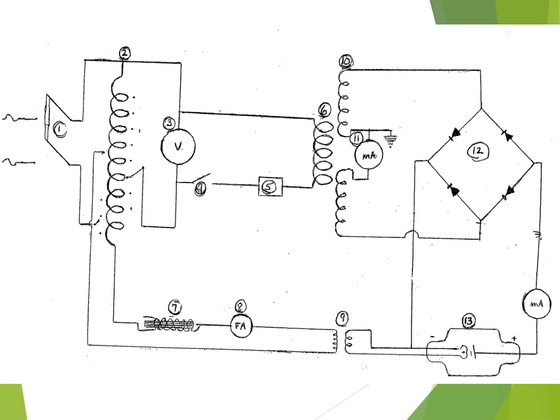Now here's a picture of our circuit. I'm going to start off with the first part. The very first portion is the primary circuit, and that's everything from number 1, which is the electrical source, including the main breaker, the auto transformer with the line voltage compensator. It includes number 3, which is called a voltmeter. It includes the exposure switch, which is number 4. It includes the timer circuit, which is number 5. It includes number 6, which is the primary side of the high voltage transformer, which is a step-up transformer.